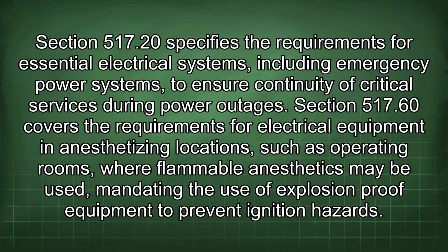Section 517.20 specifies the requirements for essential electrical systems, including emergency power systems, to ensure continuity of critical services during power outages. Section 517.60 covers the requirements for electrical equipment in anesthetizing locations such as operating rooms, where flammable anesthetics may be used, mandating the use of explosion-proof equipment to prevent ignition hazards.